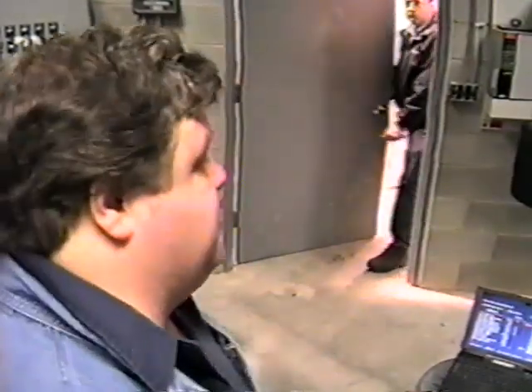So what we do is, if this sees that sump temperature dropping below 70, it's going to lock out the underfloor heat, because we're sucking heat out of that sump for our underfloor. So it says, I've got to keep the heat in there, shut the underfloor heat off. It'll do that until you reestablish the temperature in your sump again. We're all looking at protecting and keeping this machine running. Who cares about the underfloor heat? Right, okay. There are other things that are more important, right?